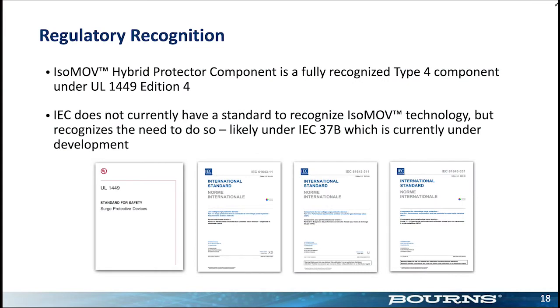Because these hybrid protectors are new, not all the standards bodies really have recognized them yet. You won't find them in there. UL 1449 edition 4 does recognize it as a type 4 component, but some of these other standards don't know what to do with these yet, but they know they need to. So they are currently in the process of writing standards around it, and it looks like it'll occur under IEC 37B, which is currently being written.